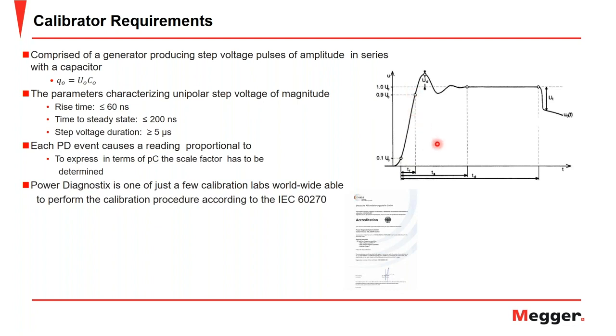The time to steady state must be less than or equal to 200 nanoseconds, which is when this wave starts and hits steady state here. And then ultimately the step voltage duration must be greater than or equal to 5 microseconds, which is the full duration starting here to the end of the step voltage here. And each of these PD events causes a reading proportional to the calibration that's taken place, to express in terms of picocoulombs that scale factor that is determined.